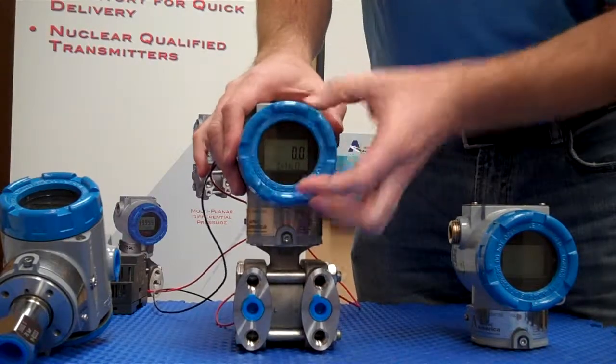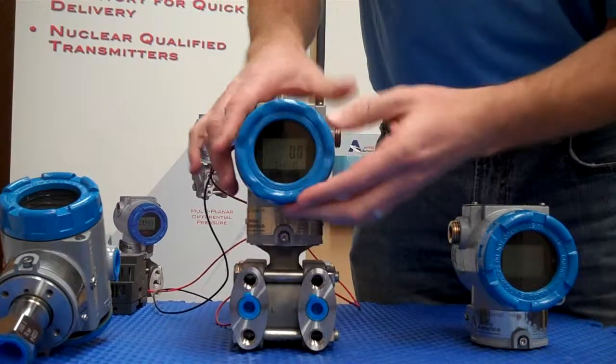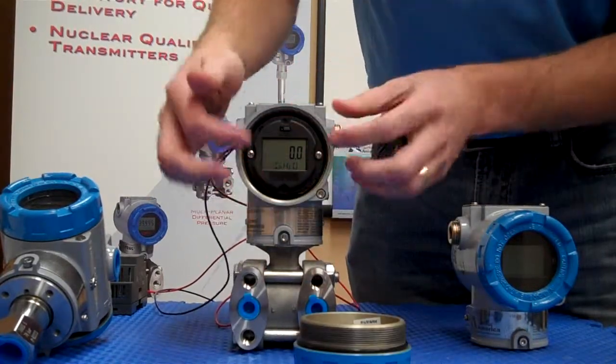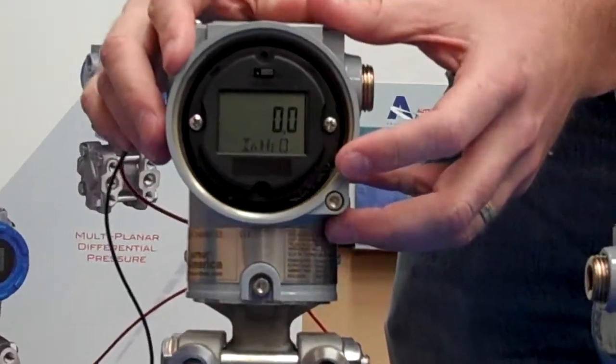As we unscrew the cover, you can see the indicating LCD. The LCD is rotatable - we can undo these screws and rotate it around. We also have the ability to change the fail position to high or low by moving this jumper.